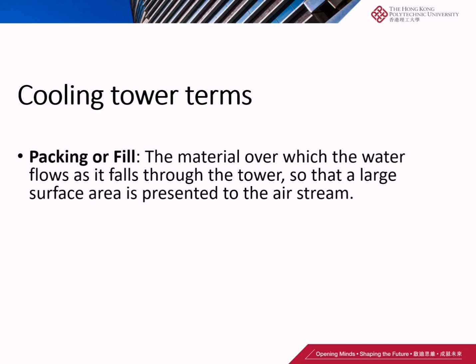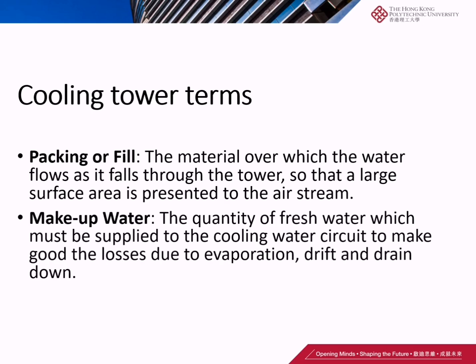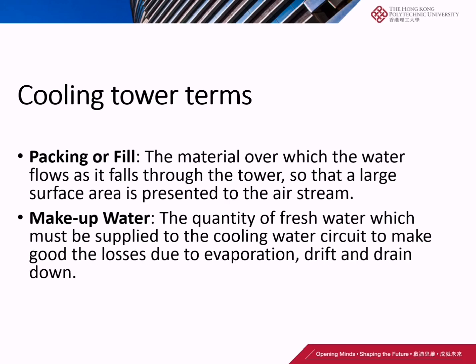Packing or fill is the material over which the water flows as it falls through the tower, so that a large surface area is presented to the air stream. Make-up water is the quantity of fresh water which must be supplied to the cooling tower circuit to make good the losses due to evaporation, drift, and drain down.